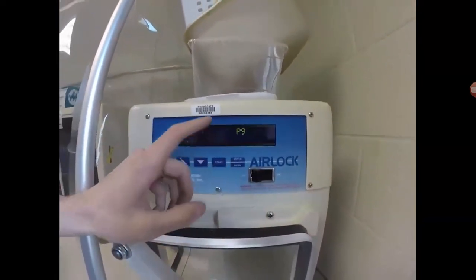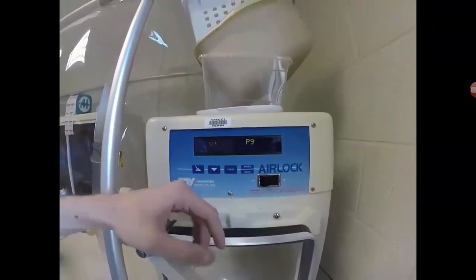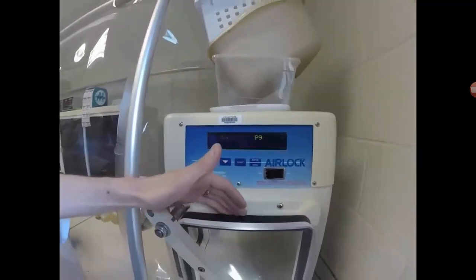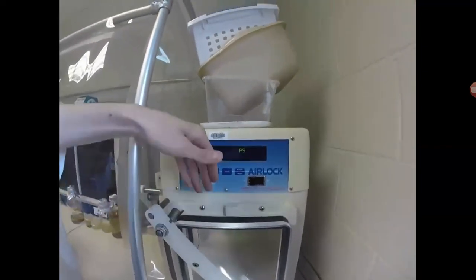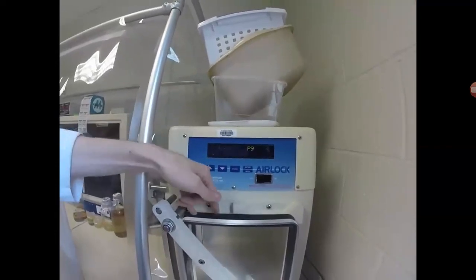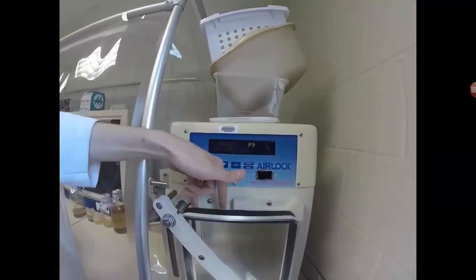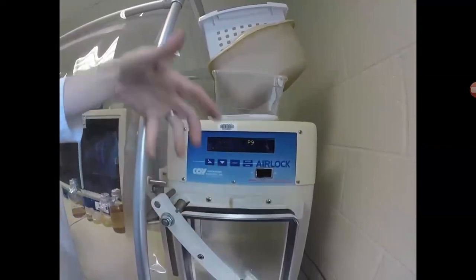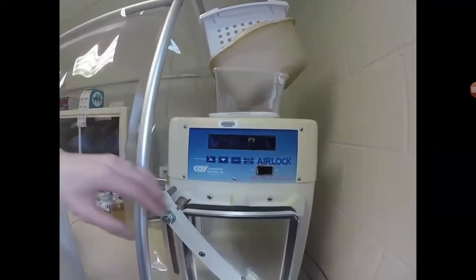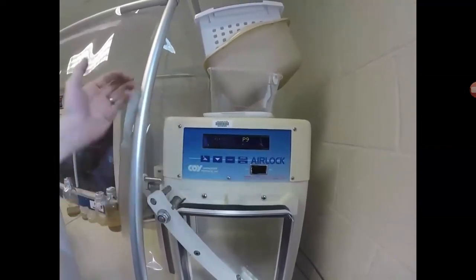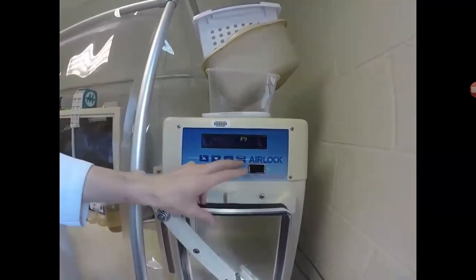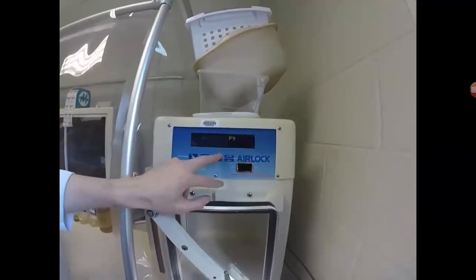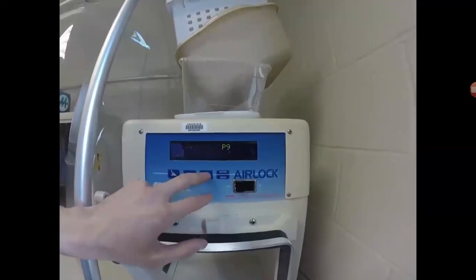Okay, so P9 is just a preset program. That's what we use all the time. It pulls vacuum once, and then it fills with nitrogen. It pulls a vacuum again. It fills with nitrogen again. And it pulls a vacuum again, and it fills with the nitrogen hydrogen mix. At which point it will say it's anaerobic, and we can then open the inside door. Okay, so we need to do that before we open this, so we don't get a bunch of air into the chamber. So if it's ready, P9, we can just press start.